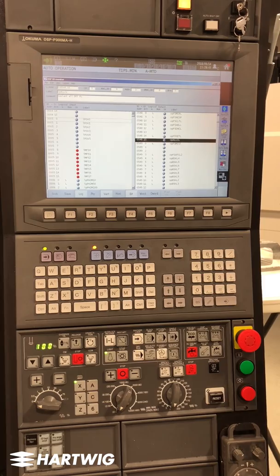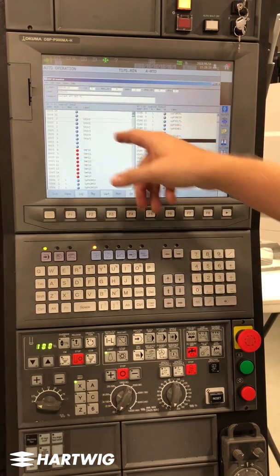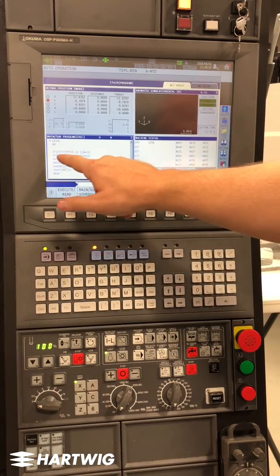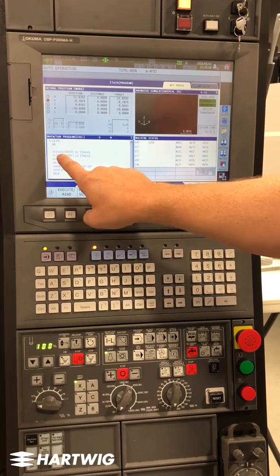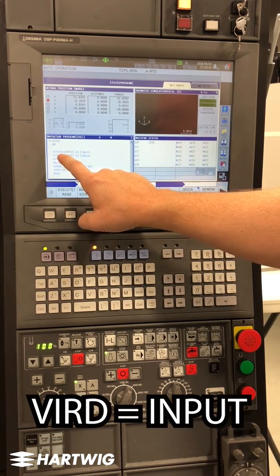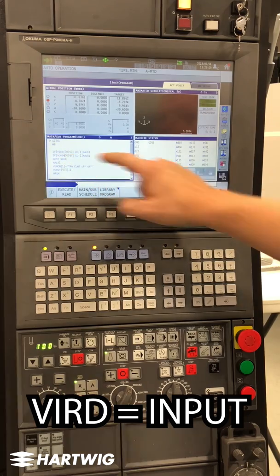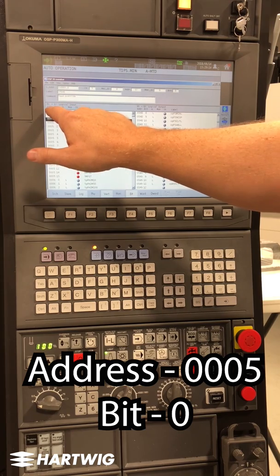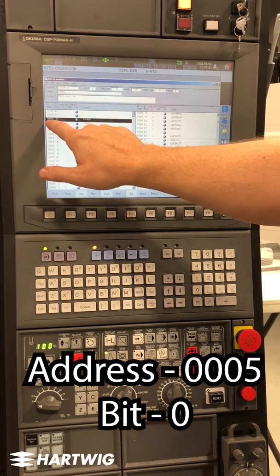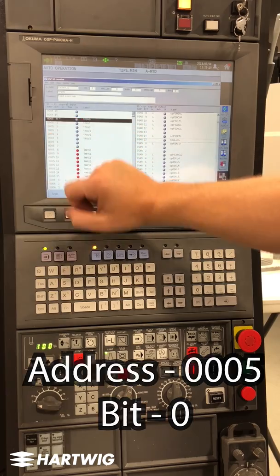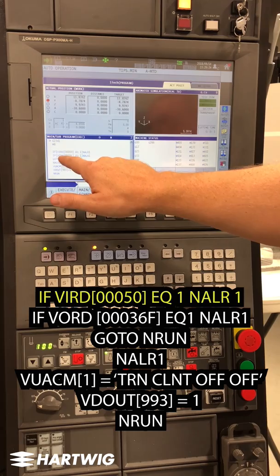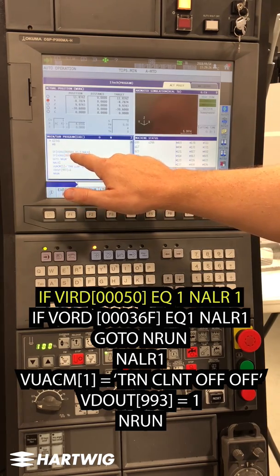What we're looking at now is a list of inputs and outputs on the machine tool — inputs on the left, outputs on the right. Inside the code, I have an if statement using a VIRD, VIRD being an input. It consists of five digits: those five digits are the address, 0005, and the bit, 0. So inside my code, I have VIRD 00050.